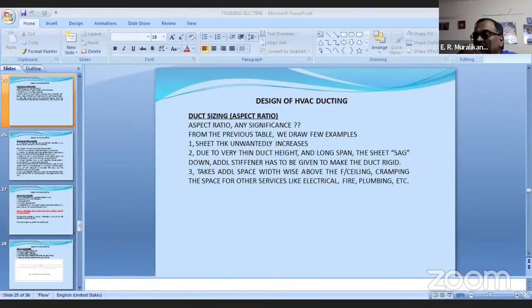What is optimal? In any comfort application, I would say up to 10,000 CFM, you go for around 900 to 950 FPM. For 10,000 to 18,000, you go for maybe 1,000 to 1,200. And when you go above 20,000, the highest limit is 1,400 FPM. Don't go beyond 1,400. This is my view, because I've seen various calculations. I'm just sharing a few of my experiences.